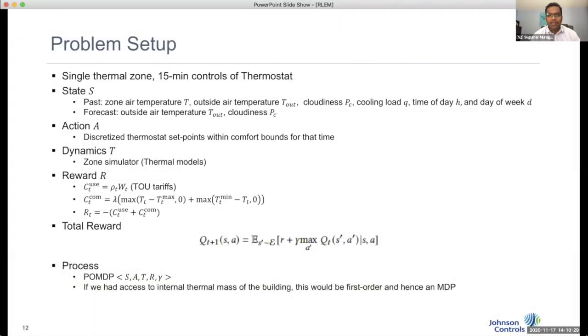We model a lobby, one hall in a building, and assume 15-minute control slots. Every 15 minutes we send a control to the thermostat to change its set point. The state itself is the past zone air temperature—the indoor temperature in the zone observed over past several slots—and the outdoor air temperature also observed over several slots, cloudiness and cooling load in the building observed over several slots, plus higher-level time-of-day and day-of-week information. We also use forecasted information such as what the outdoor air temperature will be over the next several hours and what the cloudiness will be.